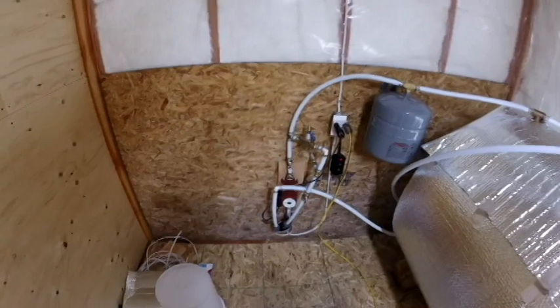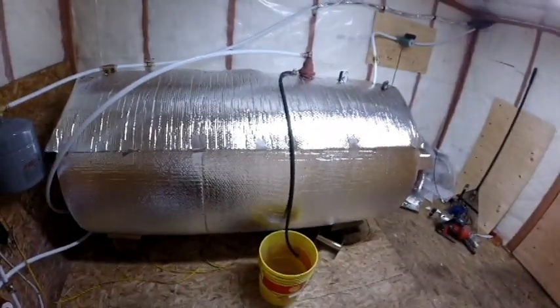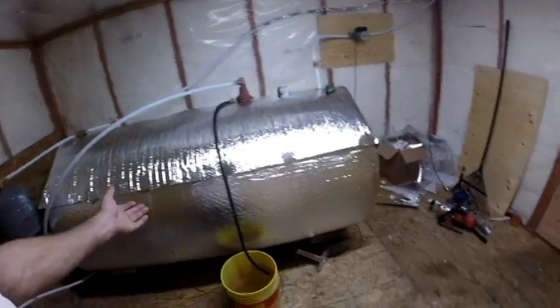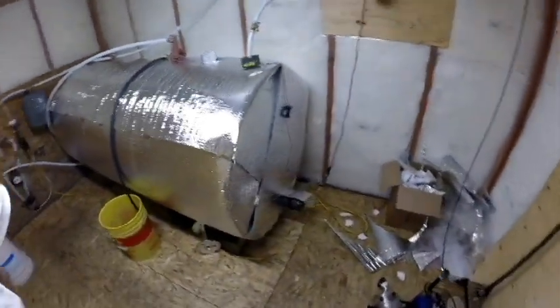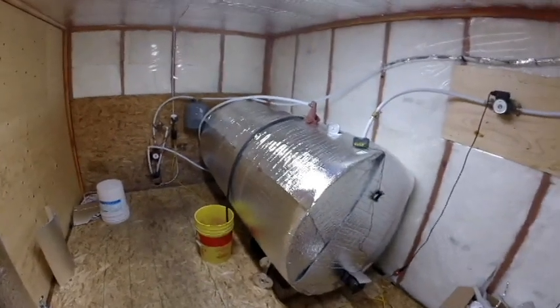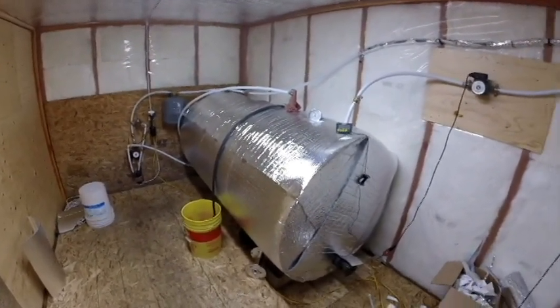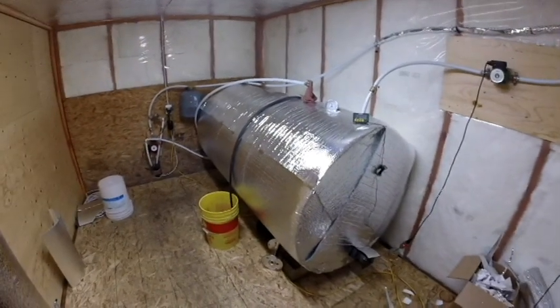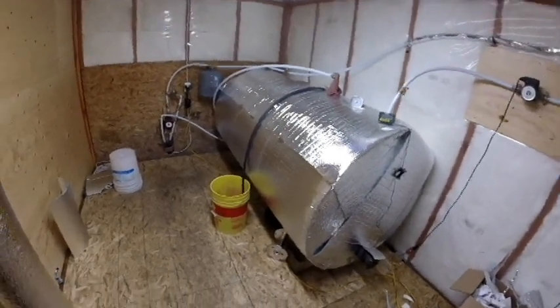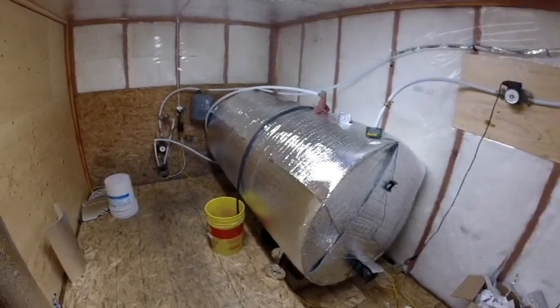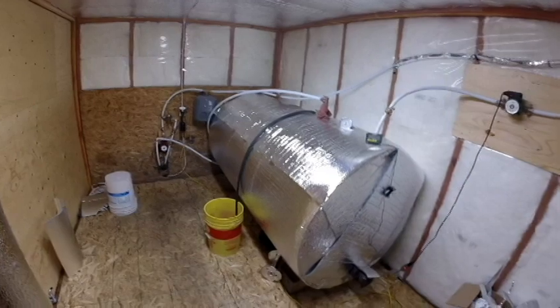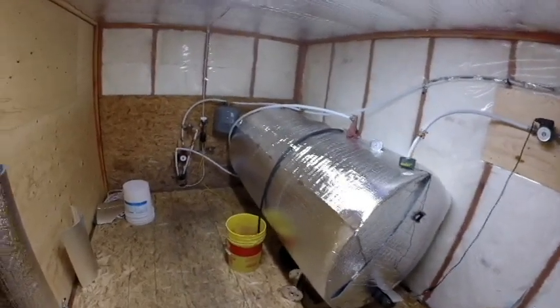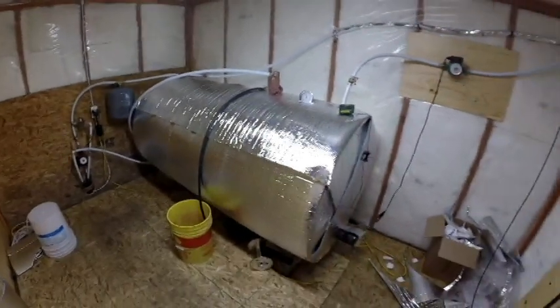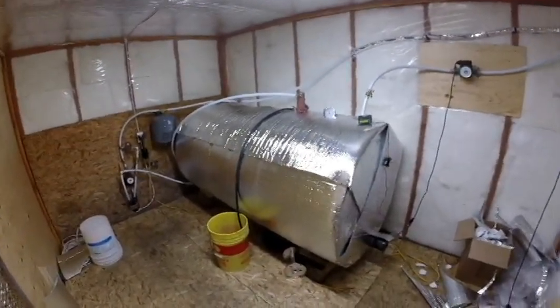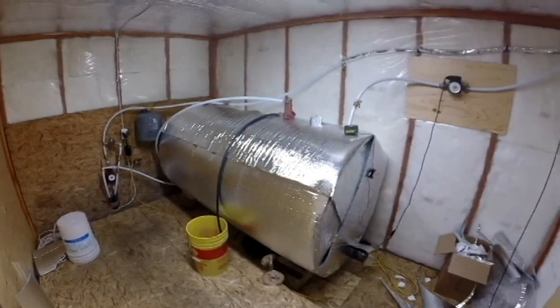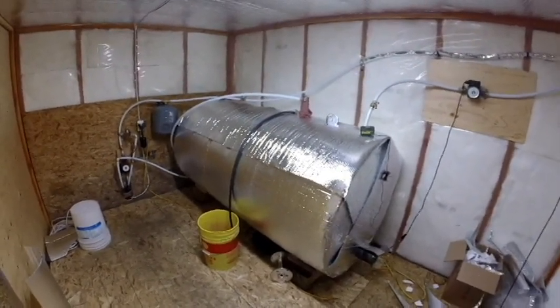It works quite well. You know, it's insulated, holds a lot of heat. 400 gallons you may think is a lot of hot water, but honestly, if I get this tank up to 190 degrees and I shut the boiler down at night, this tank will only heat the house through the night, depending on even how cold it is outside. So how much heat load my house is taking determines how long this hot water will last. And it doesn't last long. Basically on 400 gallons I can get only about 12 hours of heating to keep the house warm at night.